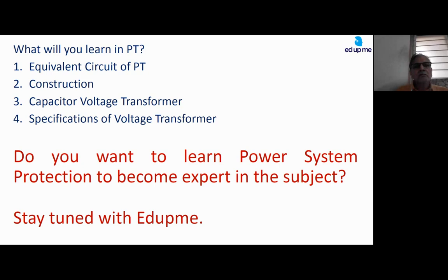Why power generation at 11 kV? Why don't we use 66 and 132 kV? The question, as I understand, is why power generation is at 11 or 15.75 or 22 kV, and why not at 66 or 132 kV directly, so that we may not have to use the GT, generator transformer. The generator, particularly the steam turbo alternator, is already running at 3000 RPM. So all rotor parts are highly stressed because of centrifugal forces.